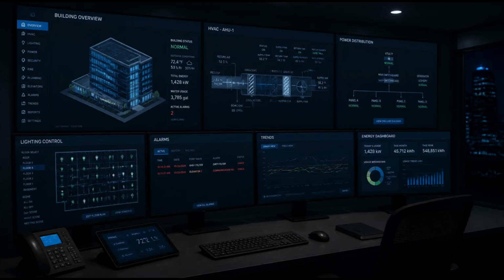Fans reduce their speed. VAV boxes close partway, delivering only a fraction of the airflow they maintained during occupied hours. Chillers may cycle less frequently or operate at reduced capacity. Boilers maintain water temperatures sufficient for protection against cold, but do not heat aggressively. The building breathes more slowly. Air still moves, but often at a lower pace. This is an important distinction.